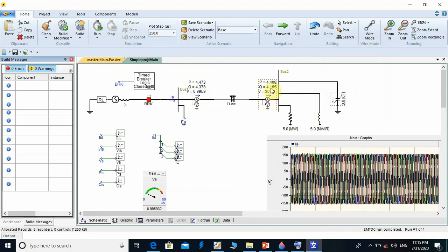You see here there is more voltage drop on this line because this line is too long, 50 kilometer. At no load, as Ferranti phenomena, you will get here over voltage, but with loaded you will get, this is a bad aspect of long transmission line or long line.